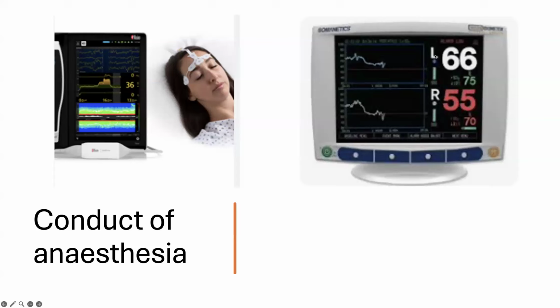So we've got L here, which stands for the left hemisphere, and the right hemisphere, and the probes are mainly stuck onto the cortical area. When there's a drop of 20% or more, you can see the change in color. This signifies that some action needs to be taken.